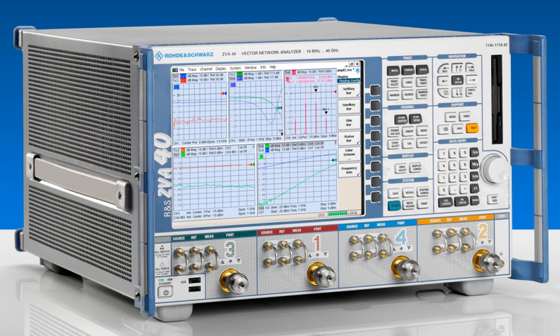The first steps, prior to actually starting the user calibration, are: visually inspect the connectors for any problems such as bent pins or parts which are obviously off-center. These should be thrown away, as mating damaged connectors with good connectors will often result in damaging the good connector. Clean the connectors with compressed air at less than 60 psi. If necessary, clean the connectors with isopropyl alcohol. Gauge the connectors to determine there are not any gross mechanical problems.